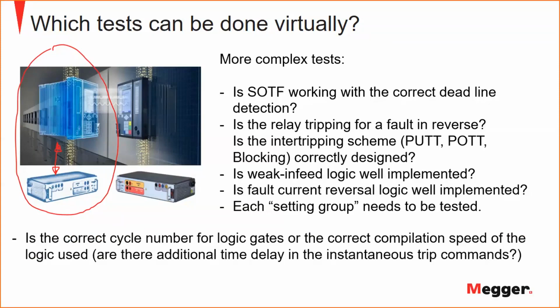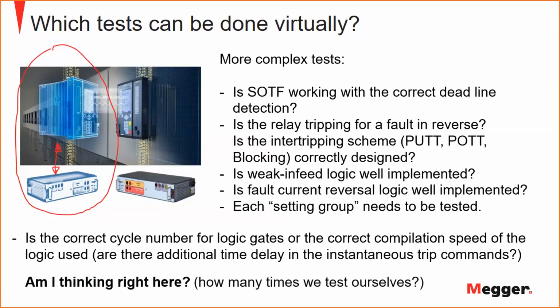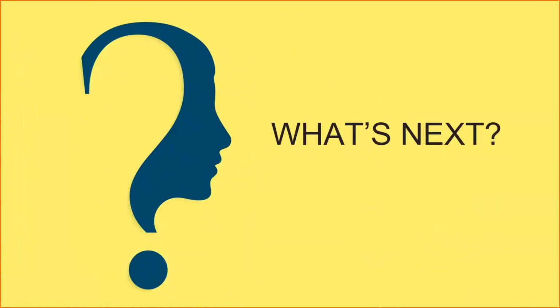This is a typical problem of testing in the substation when you test your configuration, and all of this can be done by measuring the disturbance recorder. So you don't need to go there on site. You can fix things before. And also, remember, what we do when we test, and don't tell me this is not true, the majority of the times we are not testing the relay, we are not testing the test set, we are testing ourselves. Did I understand correctly here? Did I implement the logic correctly? And maybe the customer will say, no, this should not happen in this case. And then that is when you, in a substation, unfortunately, need to change something because you misunderstood. So, what is next?